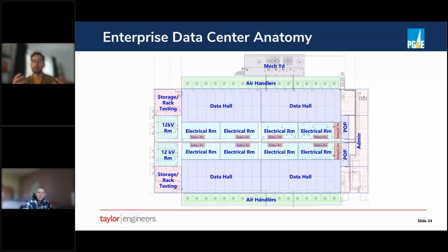so essentially, I kind of glossed over what a UPS is, or uninterruptible power supply, but the basic idea is that there's a brownout or a blackout in the data center and you need to transition over to generator power, that UPS provides something to allow you to ride through before the generators kick on. And those batteries are what provide the power to the distribution before the generators start.